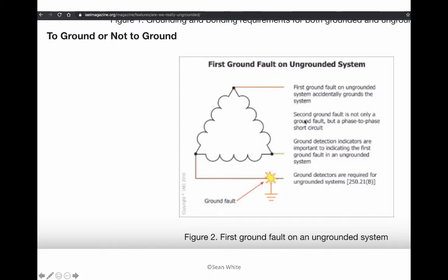But then if you have a second ground fault, that's when there's a problem. So it's not only a ground fault, but a phase-to-phase short circuit. So as you can see, the first fault just grounds the system, makes it like a grounded system. It's not something that you would even potentially have to shut the factory down for. So when you have these big factories, you might have engineers that are experts in this, monitoring things as they're going on.